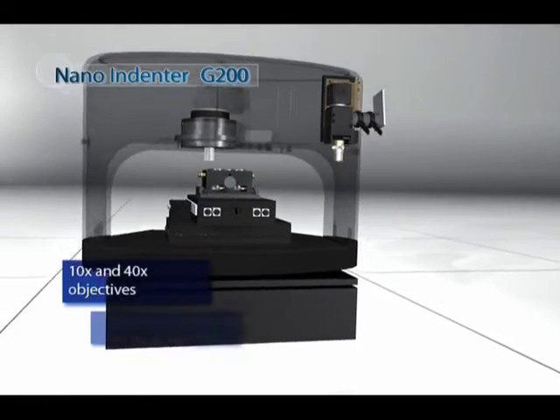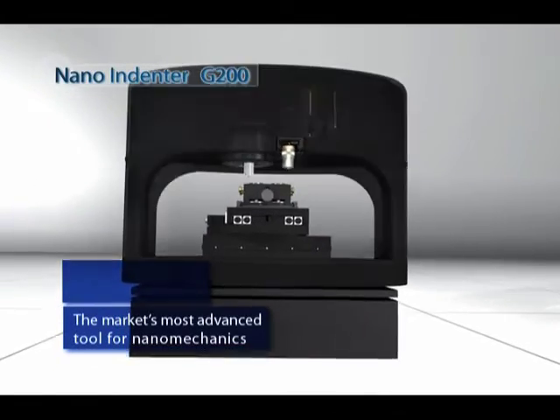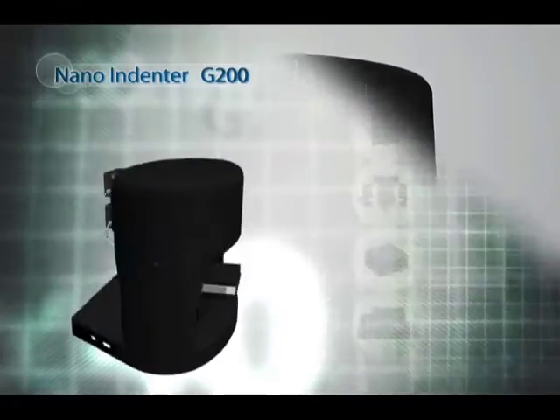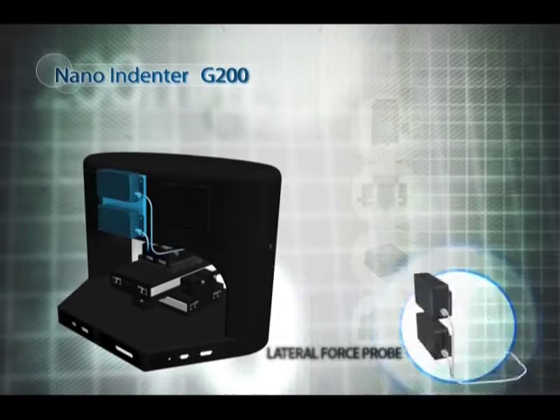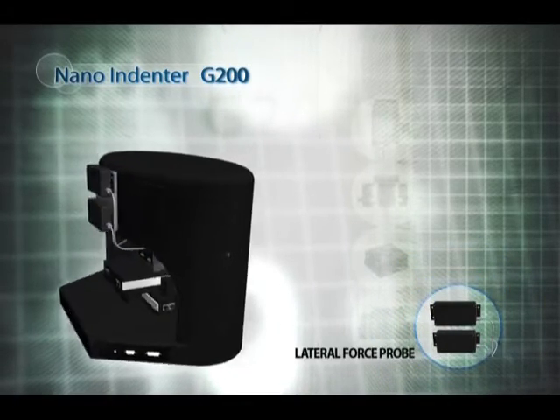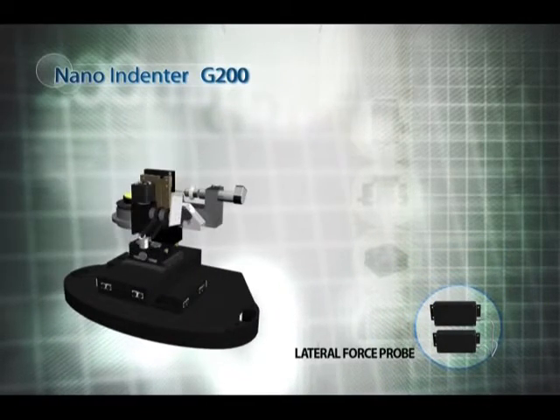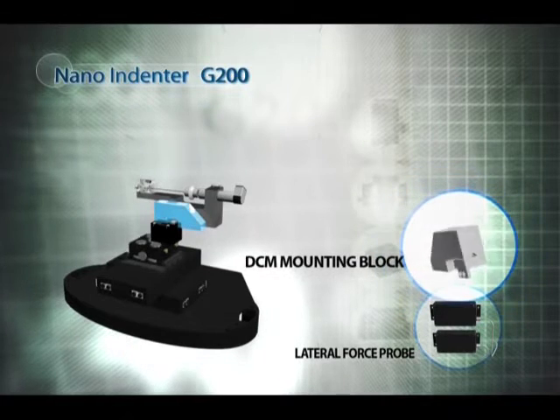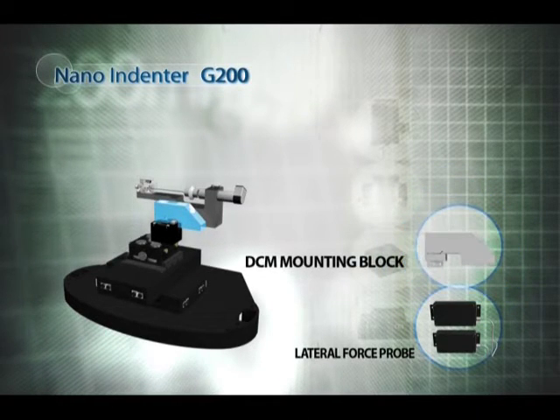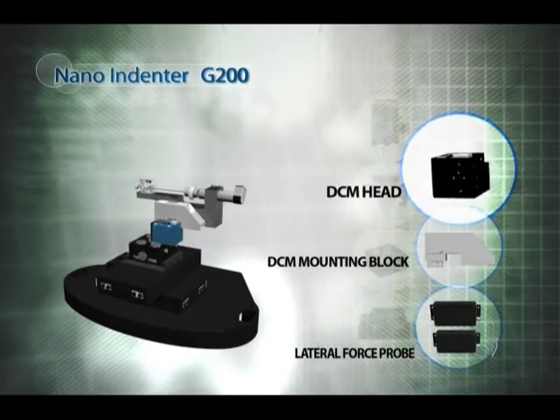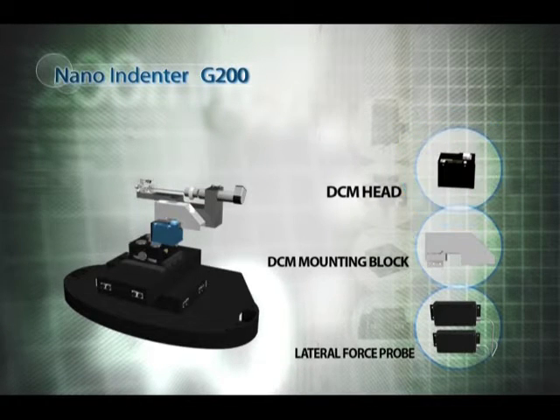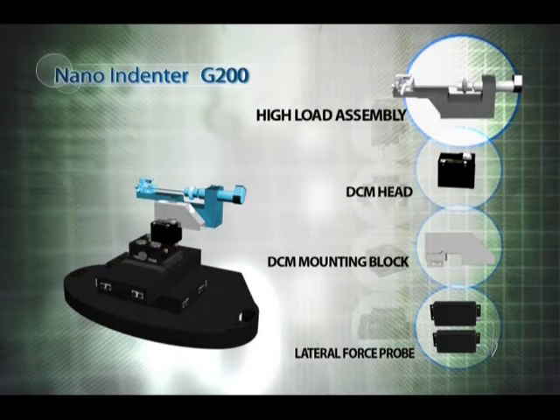The nano indenter offers many options to expand the capabilities of the tool. Some options include lateral force probes for tribology and MEMS applications, the DCM transducer for ultra-low load and ultra-high resolution indentation, and the high-load assembly for indentation up to 10 newtons of force.